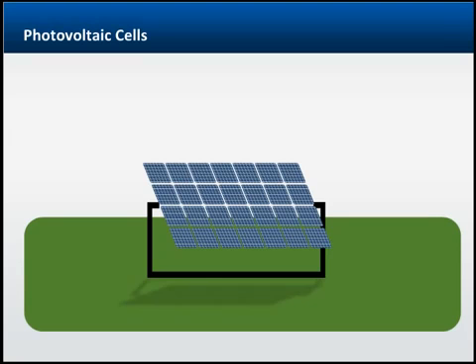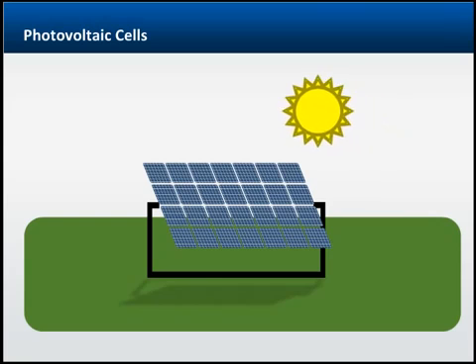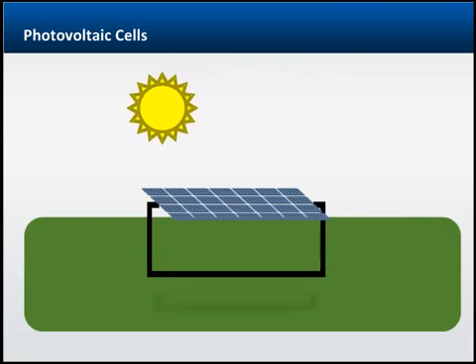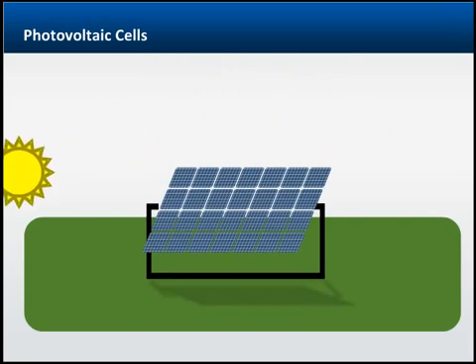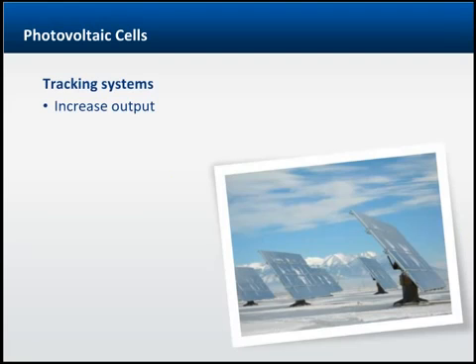The alternative is to build a tracking system. A tracking system moves the array throughout the day, following the movement of the sun. Tracking systems may be one-axis, which follow the sun's movement from east to west across a single day, or two-axis, which track daily movement as well as the sun's movement north to south on a seasonal basis. Tracking systems increase output for the same number of cells, and two-axis systems increase output more than one-axis systems.